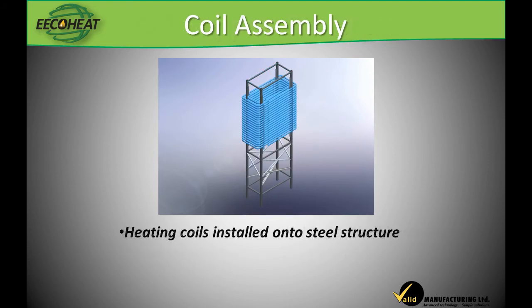The heating coils are installed in multiple concentric helical assemblies. The thermal fluid is pumped into the bottom of these assemblies and travels upwards through the spiraling coils, exiting at the top. This ensures that no air is trapped within the heating element coils.